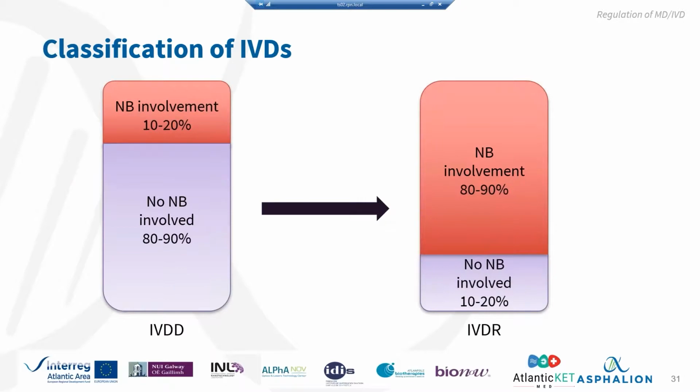What's the paradigm with this change in the classification? Well, up until now, with a directive, it was pretty easy to obtain a device that didn't require notified body involvement. On the other hand, now with the regulations, it's going to be the other way around. It's quite likely that you're going to need notified body involvement, and there are going to be just a few devices that do not require it.